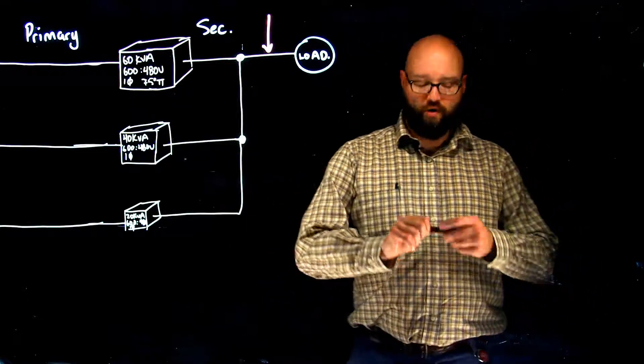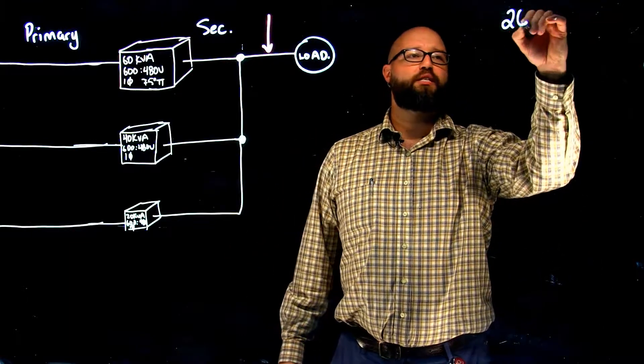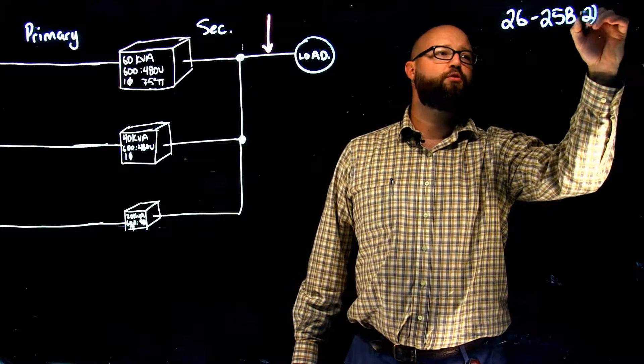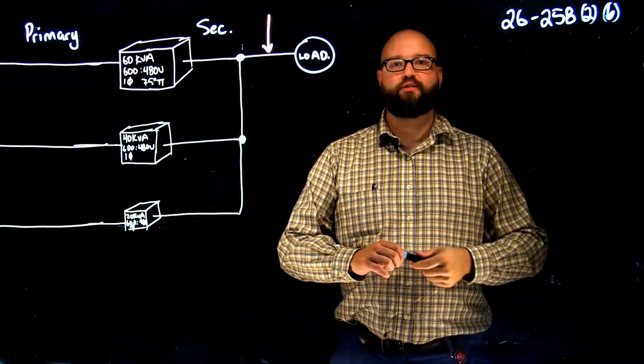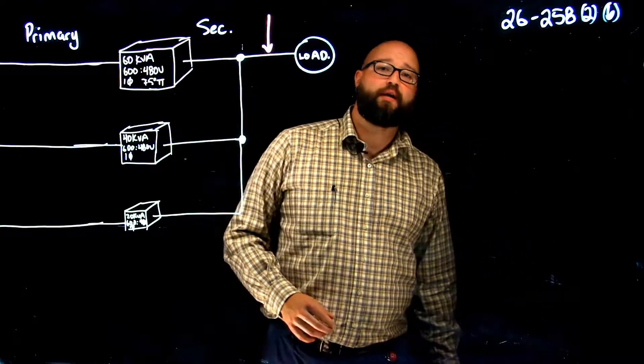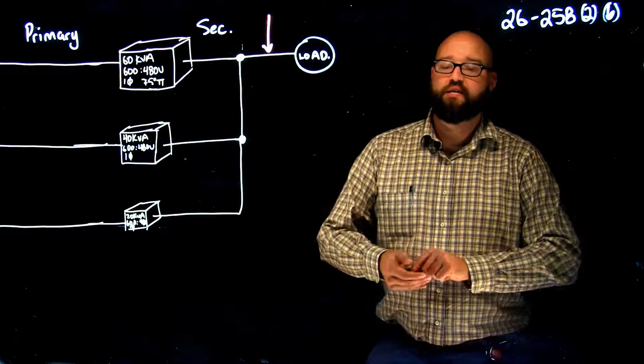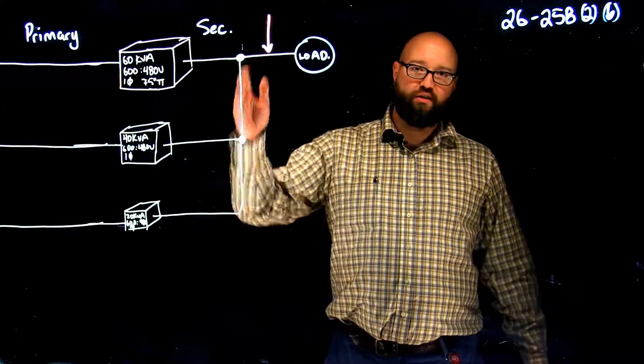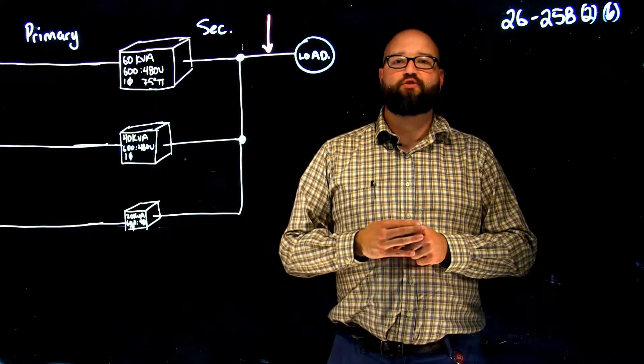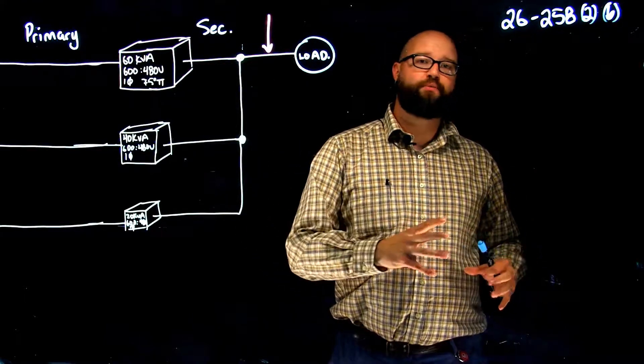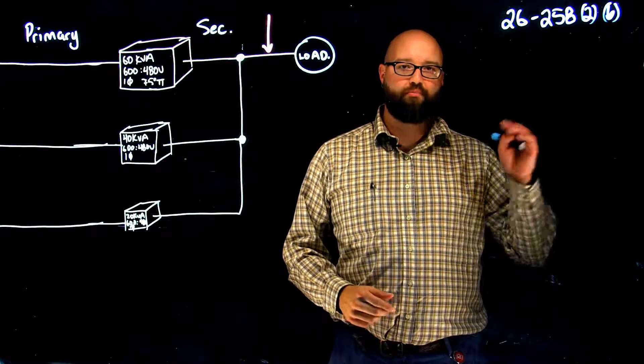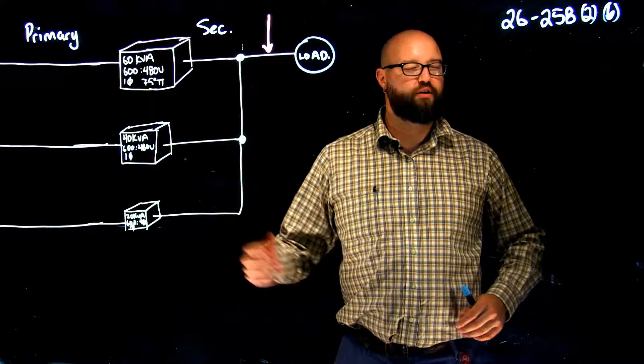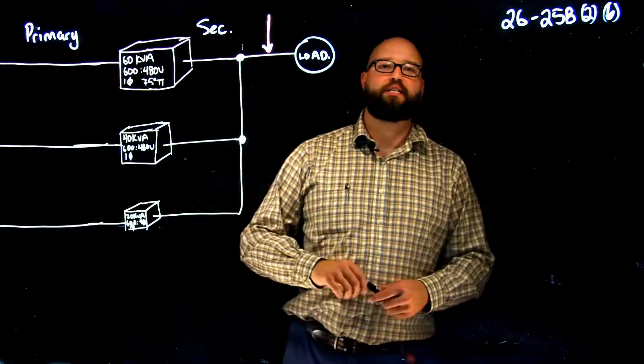So we are going to reference in this one 26258 sub rule 2 item B now for parallel secondary conductors of multiple transformers. The way the rule states is we are basically going to take the rated current of each one of these transformers, we are going to add them together, and then we are going to take 25% of that number and put it right on top. Again we're going to do a little bit differently but it'll give us the exact same result.